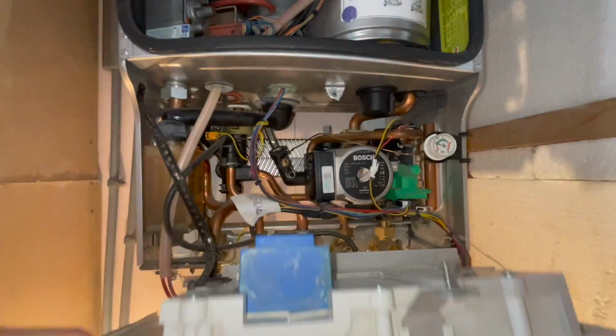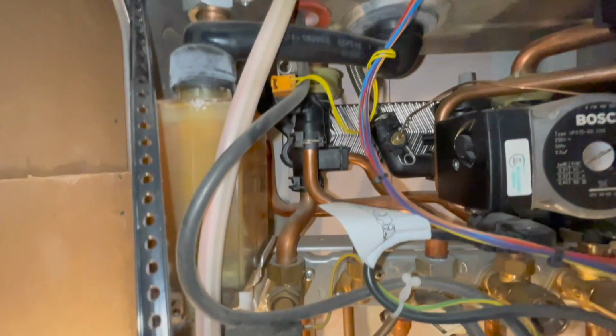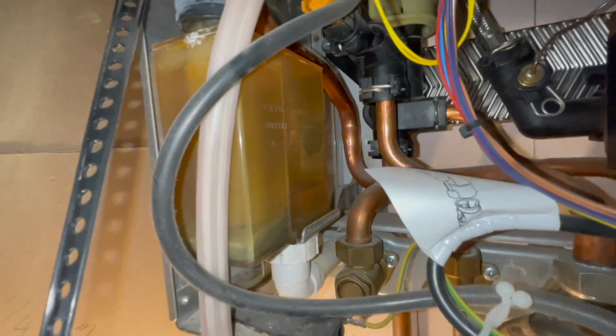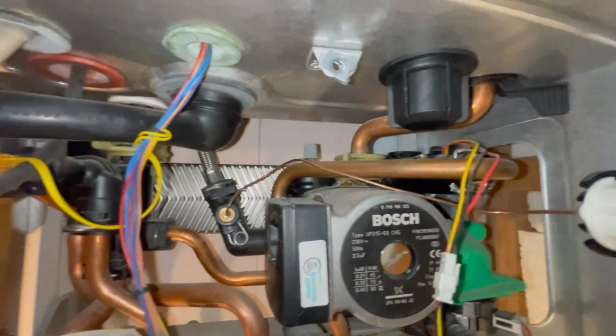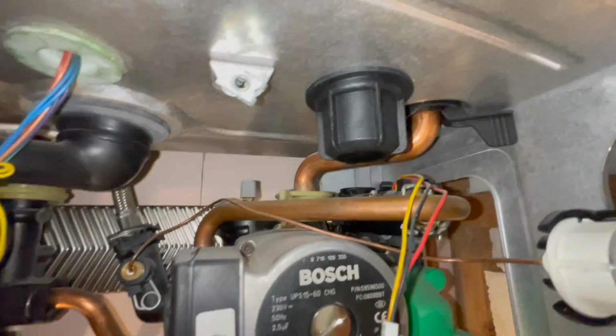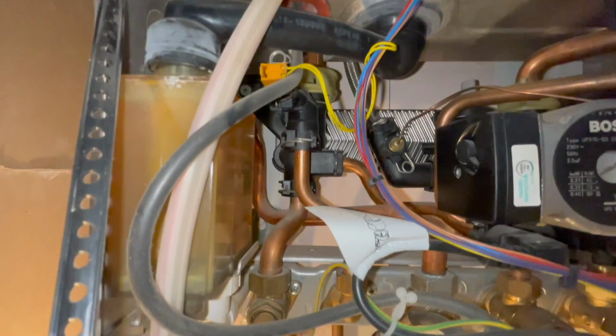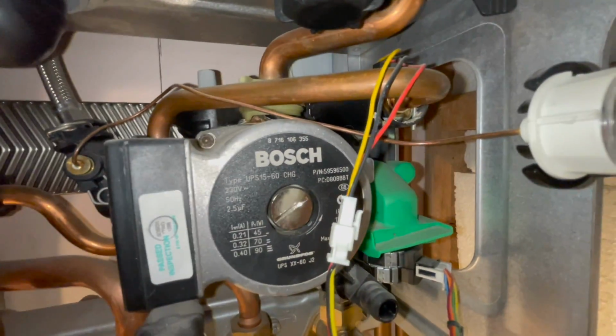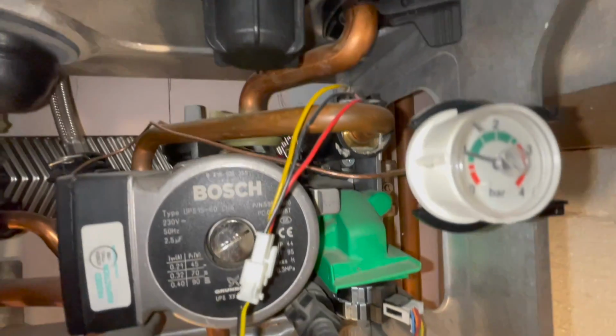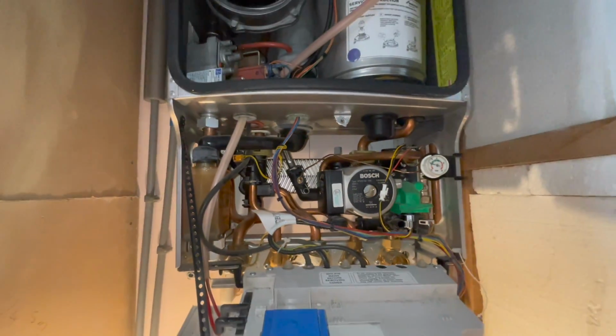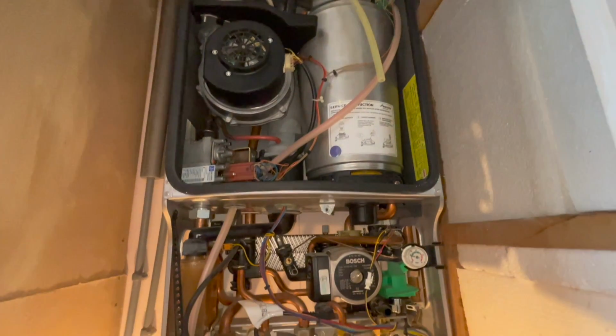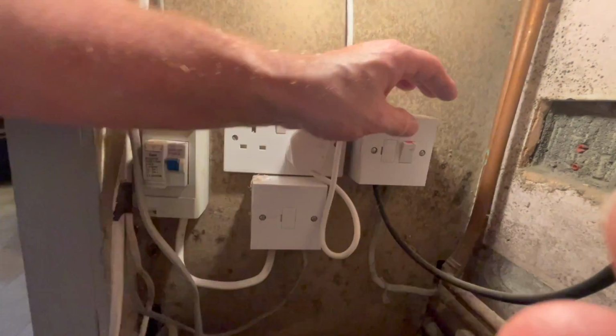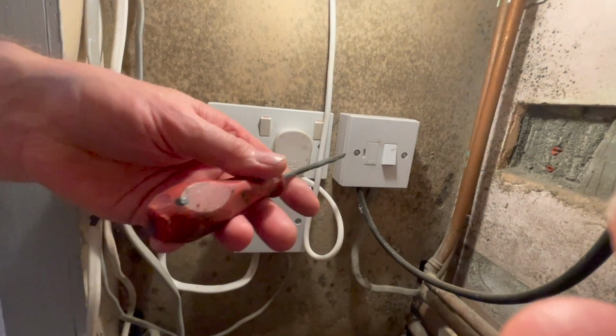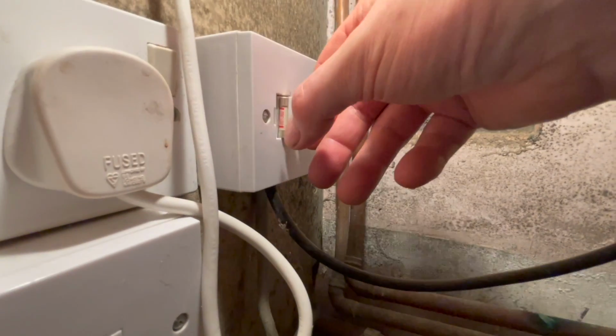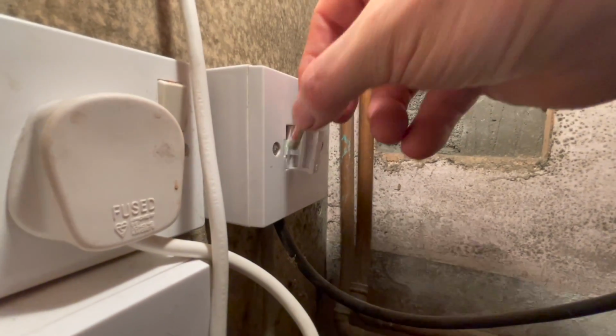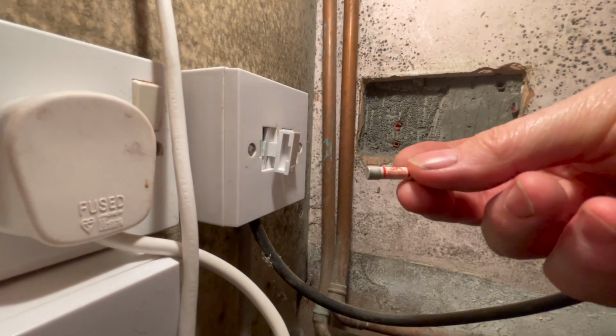Now let's take a look at the water set, see if we've got anything leaking here. So the trap needs a good cleaning out, to be expected. There doesn't seem to be any water leaks in here at all. It looks pretty clean. It's even got the green guttering on it. So that's the visual inspection, and there doesn't seem to be anything untoward. Now let's turn off the power supply and check the fuse. So the fuse is a 3 amp, so that's good.